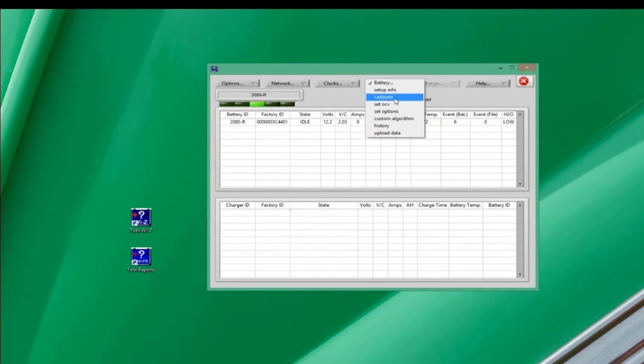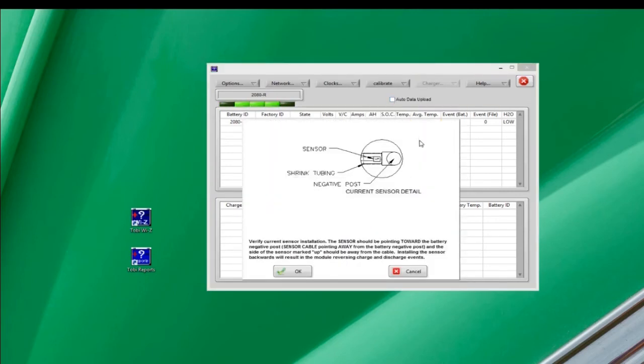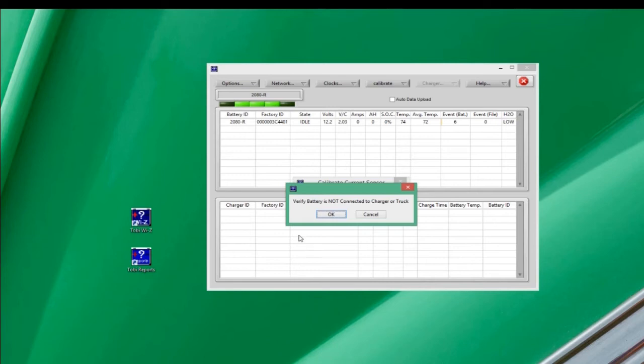And finally, to calibrate. Now, when you calibrate, you need to have a 0 reference point and then a known amp throughput. So first thing you're going to see here is a little screen that says, did you install the shunt correctly? With the little label pointing up and up close against the negative post. We've done all that, so we say yes. Next, it wants to establish a 0 reference point, so it wants to make sure that you're not connected to the charger or the truck. Okay.